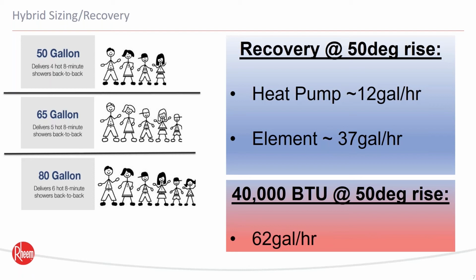We just have to get it sized correctly. So, we're pretty comfortable saying that 4 people is going to accommodate a 50-gallon, 5 people for a 65, and 6 for an 80-gallon. Now there's some tweaks that you can do to extend the life of the tank, including mixing valves, turning up the temperature. We don't recommend that you turn the temperature above 120 degrees, but maybe show the customer how to do that. It's just typically an arrow up button. That way they're mixing in more cold water when they're in the shower. That way the life of the tank lasts longer. So you're using hot water slower.